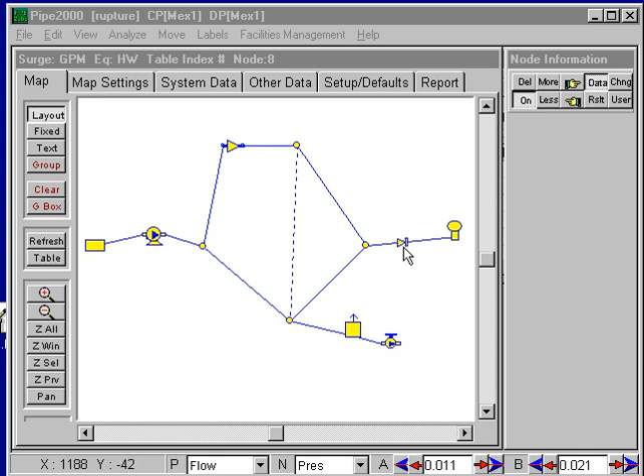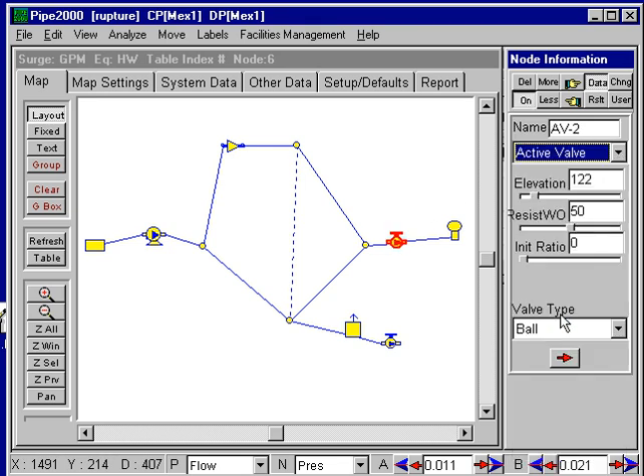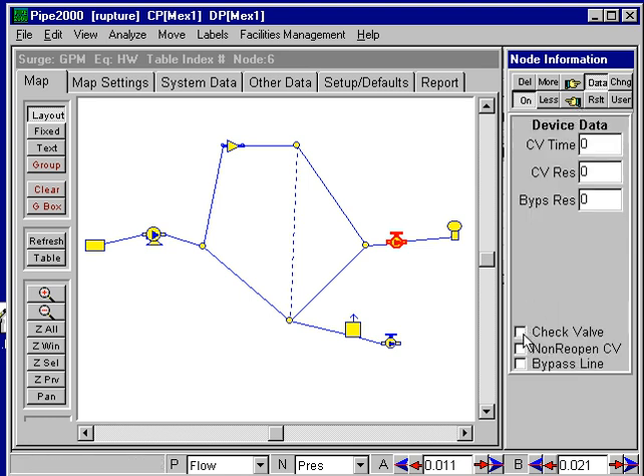As far as check valves go, in the KY Pipe program they can be anywhere in the line and they just prevent reverse flow. But for Surge, a check valve has to be associated with an active valve. So what we would have to do, if this were a surge model, is change this check valve to an active valve and put in some information dealing with a check valve — entering that there's a check valve, which would allow flow in this direction but not reverse flow.